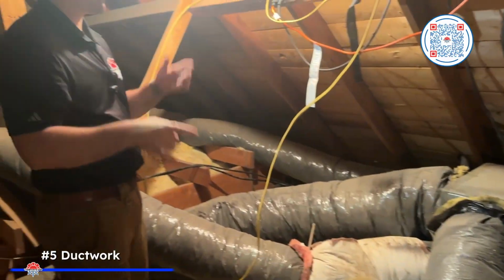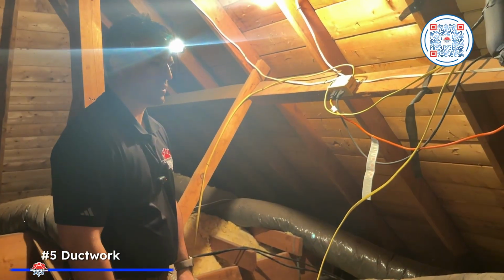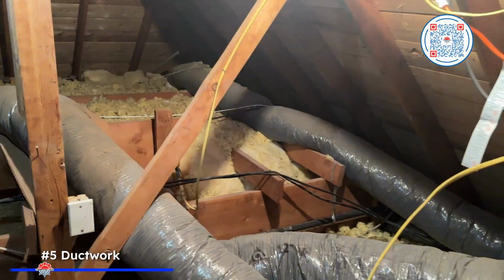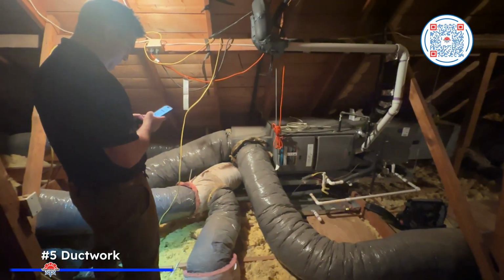Number 5 is ductwork. When we're out there doing maintenance on your system, we're looking over the entire system for anything that could shorten the life of it or cause you excessively high utility bills. Ductwork is one of those things that could do both. What we're going to be looking for is any air leaks in the return ductwork that's bringing that attic heat, typically in Oklahoma, into your system and warming that air up before it actually hits your evaporator coil. Or if it's leaking air on the return side, it could be causing your blower wheel or your evaporator coil to become dirty and then need a bigger service. So that's one side of it.